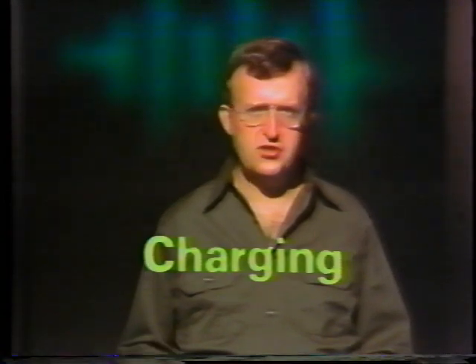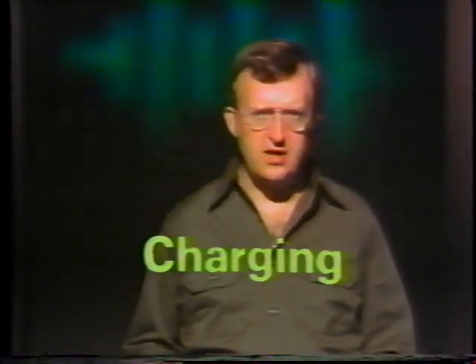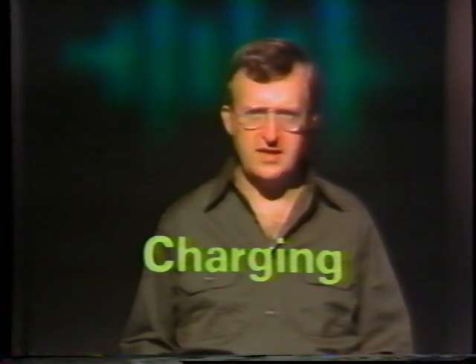We said earlier that a secondary cell has to have energy added to it before it can do anything. Adding energy to a secondary cell is called charging the cell. Only a charged secondary cell can convert chemical energy into electrical energy. Let's start by assuming that this secondary cell has never been charged. This particular cell is a lead-acid cell, one of the most commonly used types of storage cells. Both of the electrodes are made of lead sulfate, and the electrolyte is mostly distilled water, with only a very small amount of sulfuric acid mixed in.